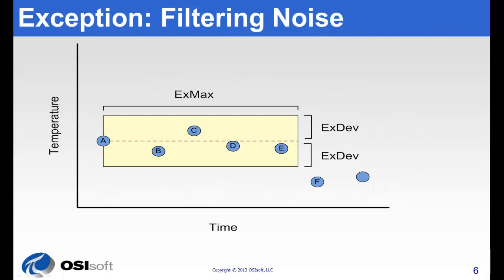There's two parts to this: exception and compression. We're going to go over the first test, exception first. Exception reporting takes place on the PI interface node before the value is ever sent to the PI server. The point of exception is to reduce the communication burden between the PI server and the interface nodes by filtering out what is obvious noise.